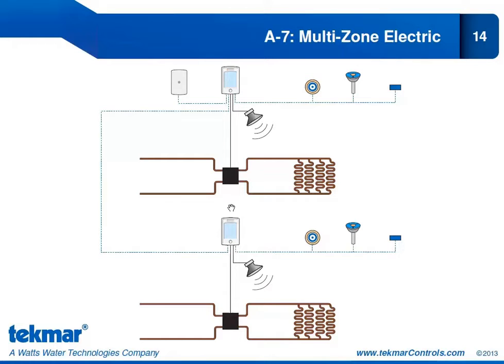Because this is a multi-zone system, we will configure zone priority. And what's nice about the 654 is we do have a special priority setting for electric applications. It would be the conditional priority setting. And the way that works is that only one of the contactors is allowed to be on at any given time. And we do that to avoid large instantaneous demands and associated large surcharges from our electric utility company. We'll talk more about zone priority later in the tekmar training webinar series, and we'll look at the three priority settings for electric and hydronic applications at that time.